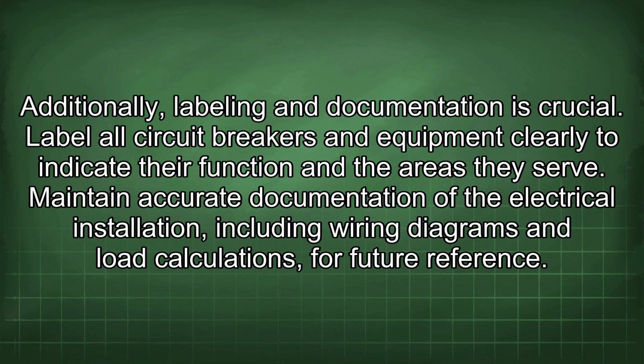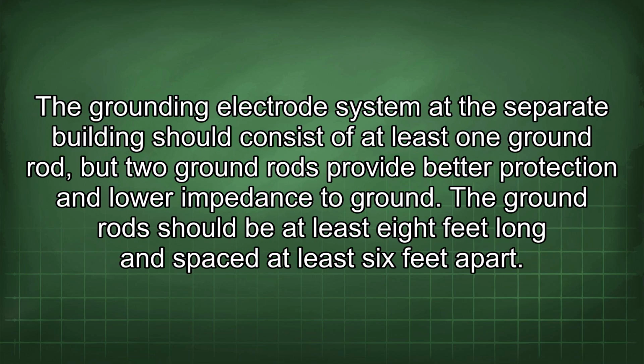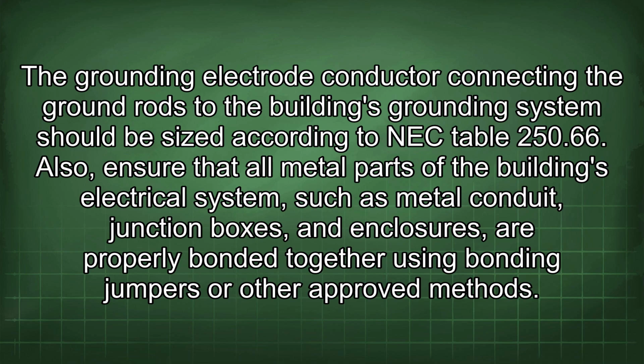Additionally, labeling and documentation is crucial. Label all circuit breakers and equipment clearly to indicate their function and the areas they serve. Maintain accurate documentation of the electrical installation, including wiring diagrams and load calculations for future reference. The grounding electrode system at the separate building should consist of at least one ground rod, but 2 ground rods provide better protection and lower impedance to ground. The ground rod should be at least 8 feet long and spaced at least 6 feet apart. The grounding electrode conductor connecting the ground rods to the building's grounding system should be sized according to NEC Table 250.66.